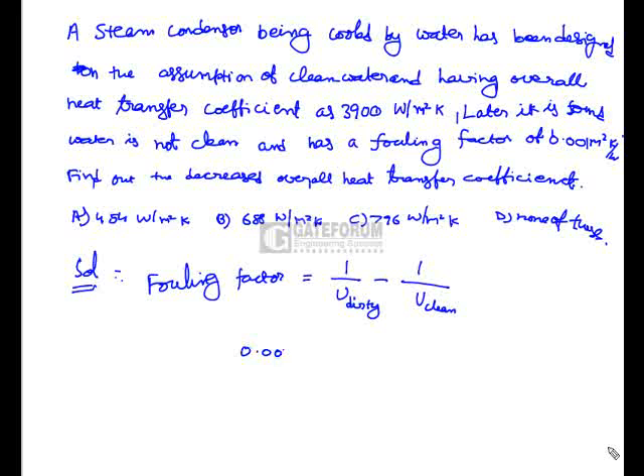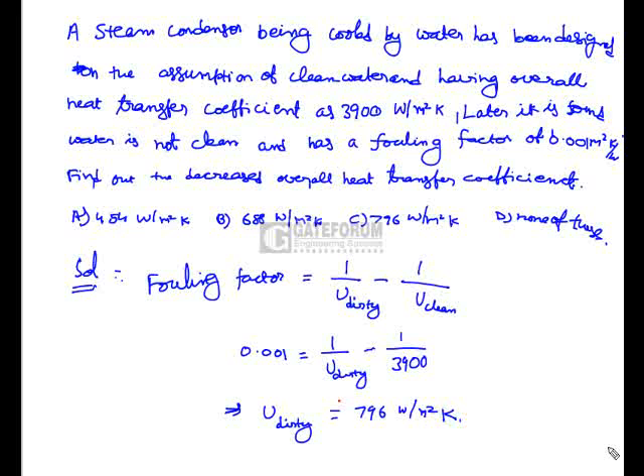The fouling factor is 0.001, which equals 1/U_dirty minus 1/U_clean. The clean water heat transfer coefficient is 3900 W/m²K. Solving, the decreased heat transfer coefficient for dirty water is 796 W/m²K. The correct answer is option C: 796 W/m²K.